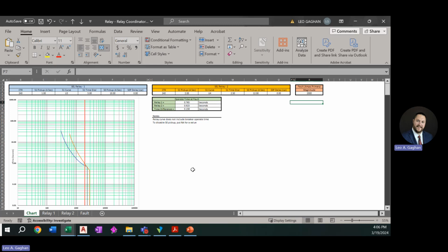That accounts for things like breaker operate time, the actual contact on the relay, how long that takes to physically move. It has to do with errors, how the relay is able to read current magnitudes, right? The relay converts that current to a value that it reads. It's not a perfect reading every time. Even the CT doesn't give you perfect currents. And then there's errors in modeling. There's all sorts of potential errors, right? That time difference, and wanting it to be so big, is intended to overcome those potential errors. So 300 milliseconds is a pretty common time difference that you might want.